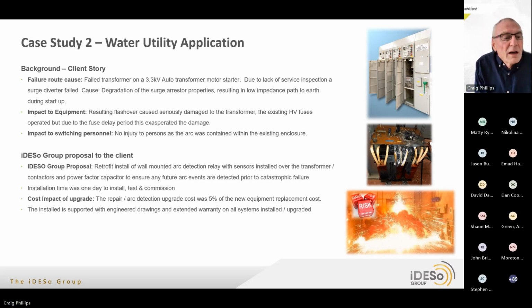So our proposal to the client. The client had this happen a number of times. He wanted us to inspect the system as the OEM manufacturer, and we proposed to them a retrofit wall-mounted arc detection relay system with sensors installed within the panel over the replacement transformer and any power factor correction system, so that the arc detected would prevent any catastrophic failure to equipment.